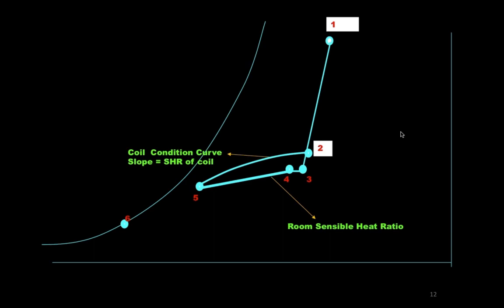So how does the system work in terms of the air handling unit operation? If you have a very large capacity due to an oversized coil, the only way you're going to change that capacity is by throttling the chill water flow rate. We throttle the chill water flow rate, what we refer to as the modulation of the chill water, and this is where it gets very interesting. When we select a cooling coil for the sensible heat factor, and we say that this coil would work for a given cooling load, we would have matched the performance of the coil in terms of the sensible and the latent cooling to what we need in the space, in the building, in the room.